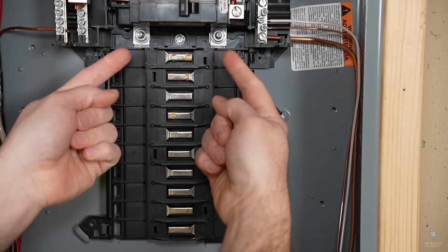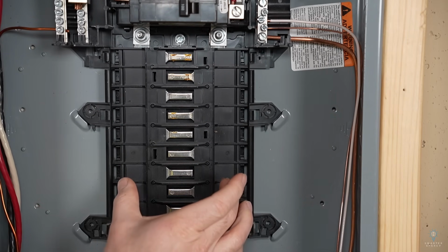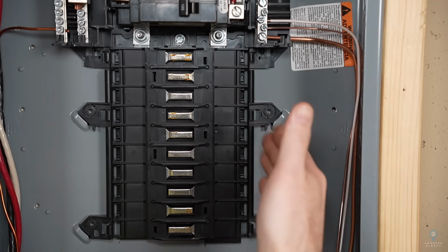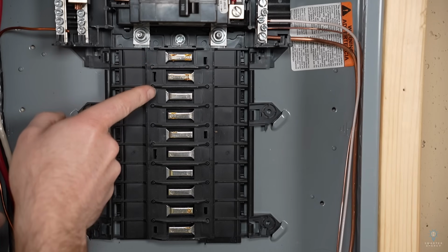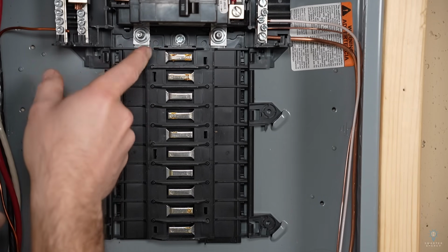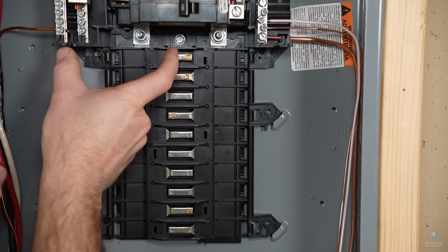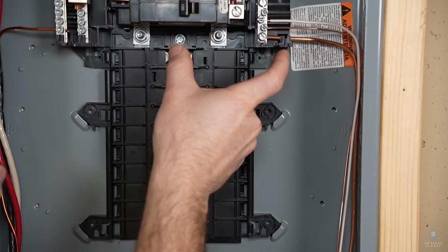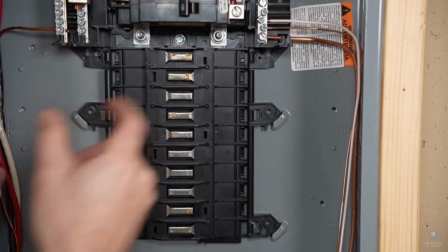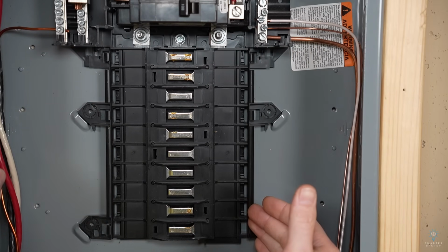So the switch side of the main circuit breaker actually feeds these bus bars, which is where we're going to connect our circuit breakers. These bus bars are insulated from the case with this plastic carrier, so they do not make contact with the case. Each one of these exposed locations is a spot for a circuit breaker. Now, each exposed spot can actually feed a breaker on either side. So this would be the location for breaker number 1. This would be the location for breaker number 2, breaker number 3, 4, 5, 6, etc. All the odd number breakers go on the left side, all the even number breakers go on the right side.